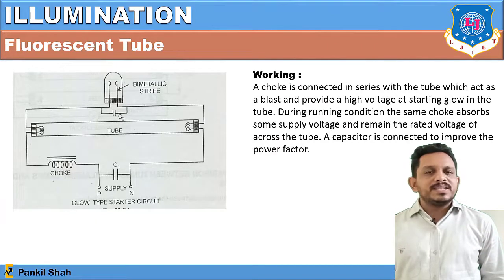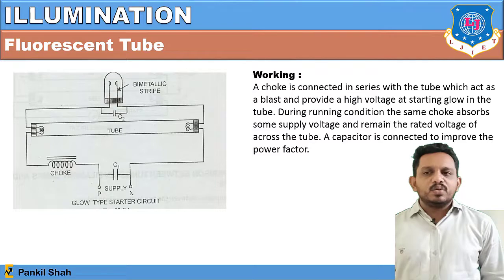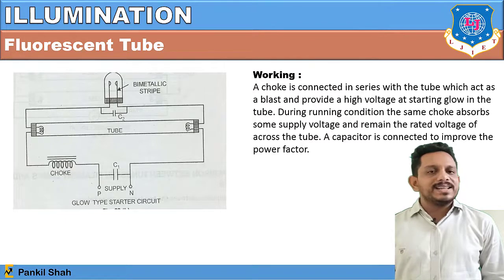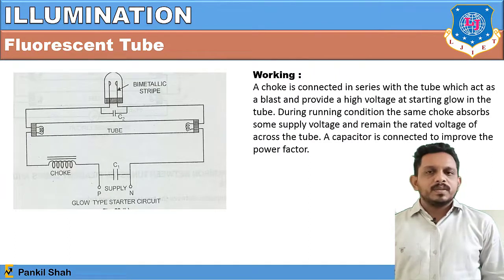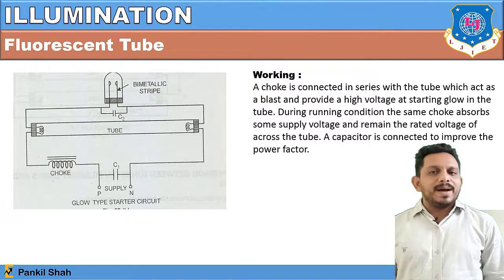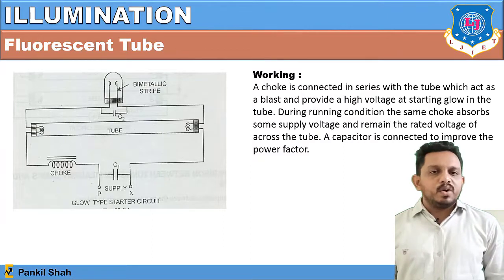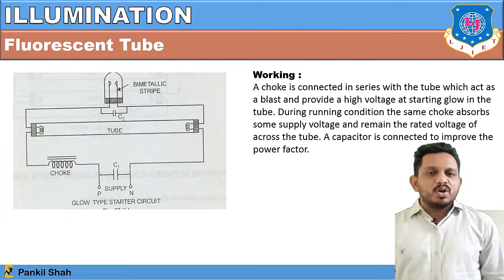The fluorescent tube has a glass tube with two filaments or conducting terminals at the corners, connected to a bi-metallic starter, a choke (ballast), and a capacitor in parallel to improve power factor. The choke is connected in series with the tube and provides a high voltage at starting, since the tube requires high voltage to initiate discharge at 230 volt supply.